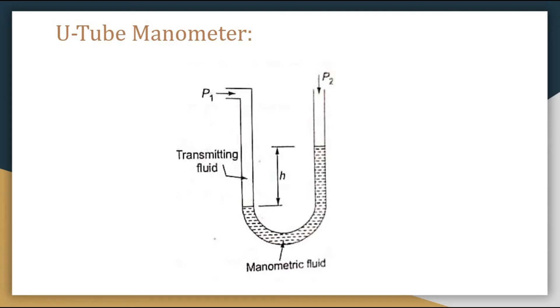An important point about the U-tube manometer: it has two pressures, p1 and p2. If p1 is the input pressure, then when p2 equals zero, it measures absolute pressure. If p2 equals atmospheric pressure, then p1 is used for measurement of gauge pressure. And if p2 is a second pressure, then p1 can be used for measurement of differential pressure. So we can use the U-tube manometer to measure three types of pressures by varying p2.